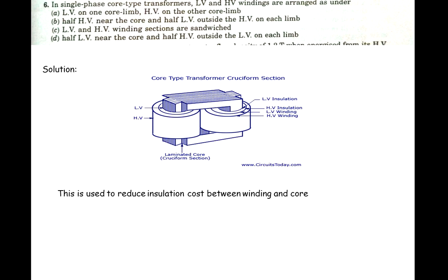Question 6: in a single-phase core transformer, the LV and HV windings are arranged as — Option A: LV on one limb and HV on the other core limb; Option B: half H.V. near the core and half L.V. outside the H.V. on each limb; Option C: LV and HV winding sections are sandwiched; Option D: half LV near the core and half HV outside the LV on each limb. Now the solution: LV winding must be placed near the core and HV winding placed over the LV winding.